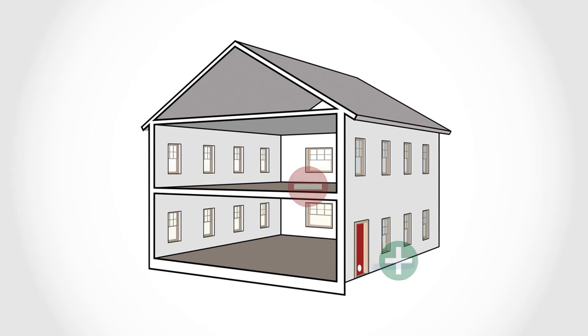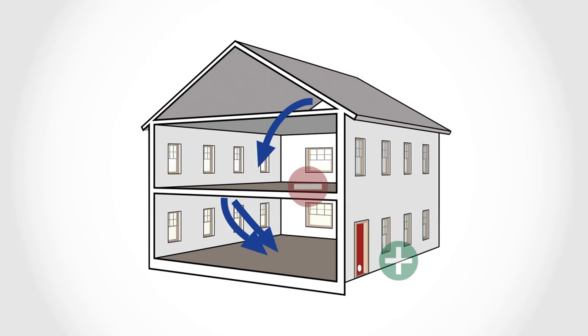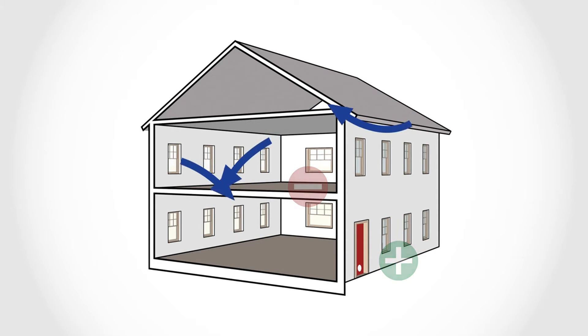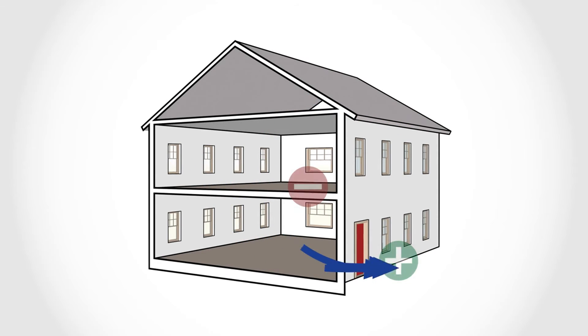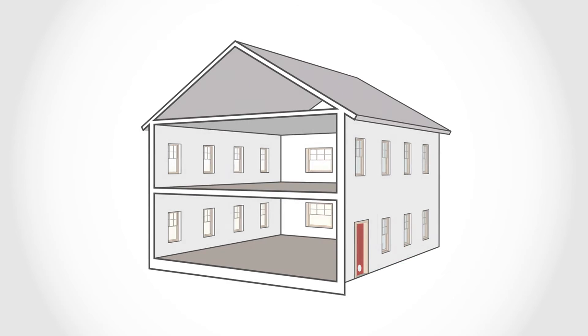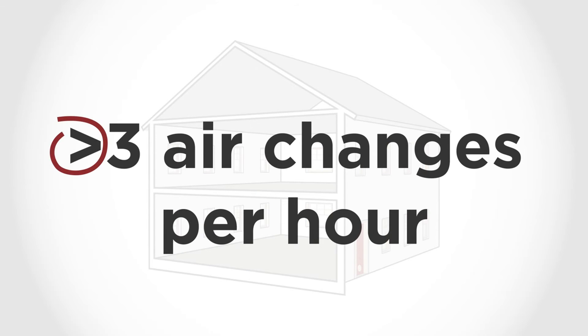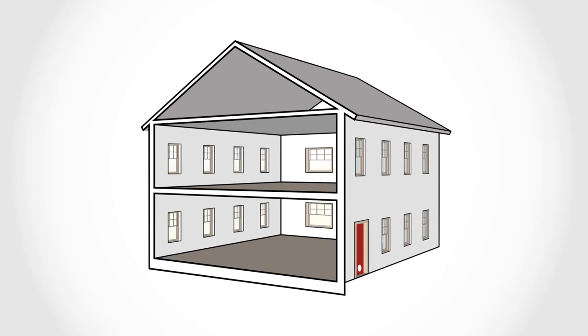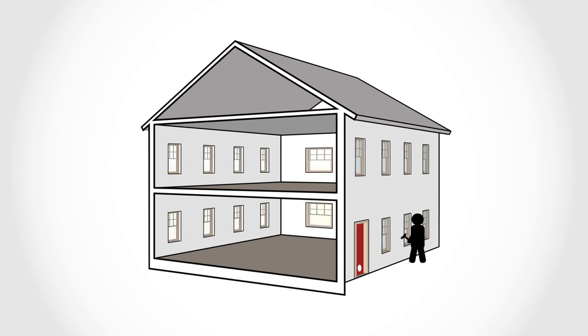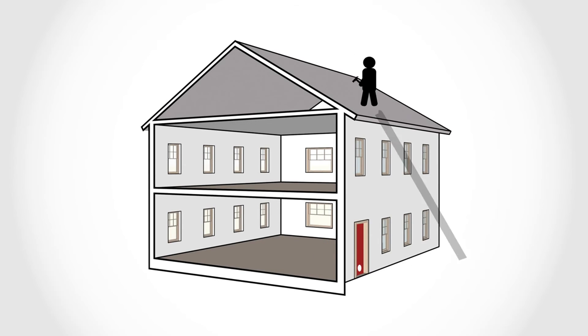The tester can then see how fast air flows through the building, measured in air changes per hour. If the blower door test shows air leakage of more than three air changes per hour, the builder will have to repair the air barrier and perform another blower door test.